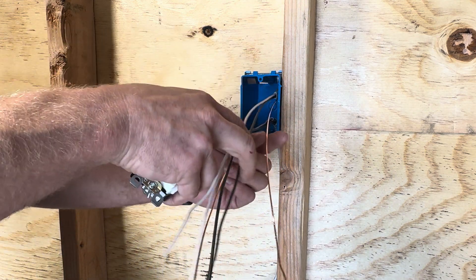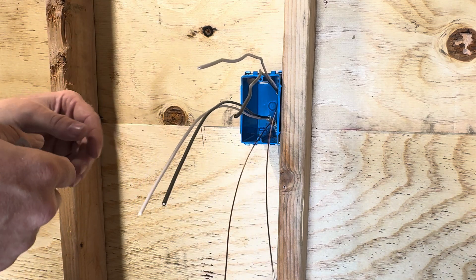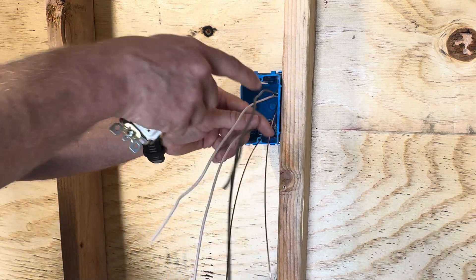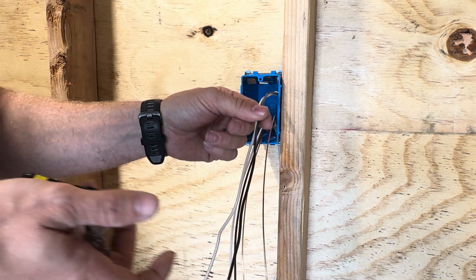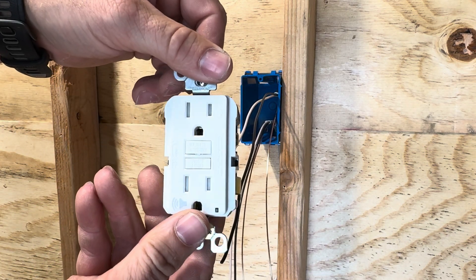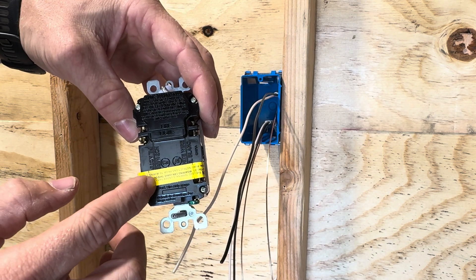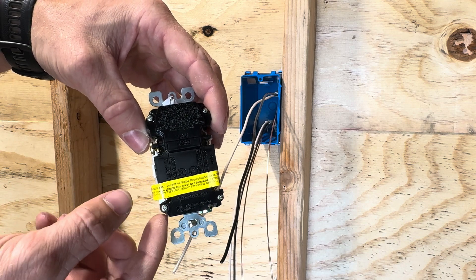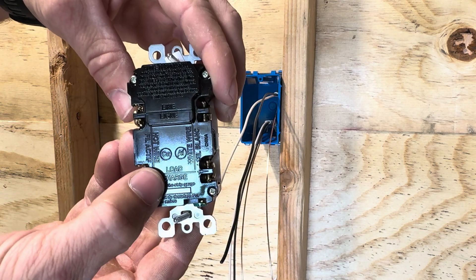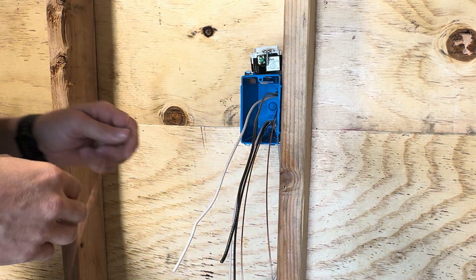You're going to take your grounds, splice and pigtail them, and tuck them back into the box. But unlike a normal circuit with receptacles, you're not going to splice and pigtail your neutrals and you're not going to splice and pigtail your hots. What you're going to do is take your line and place that at the line side indicated on the back of the receptacle.